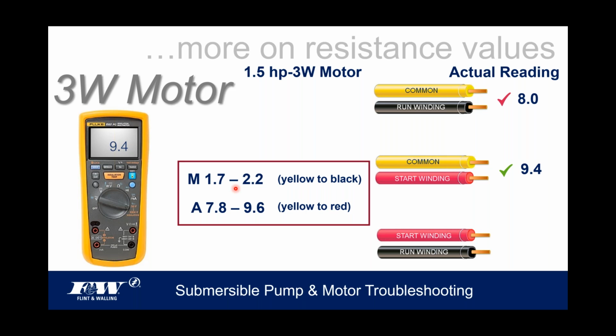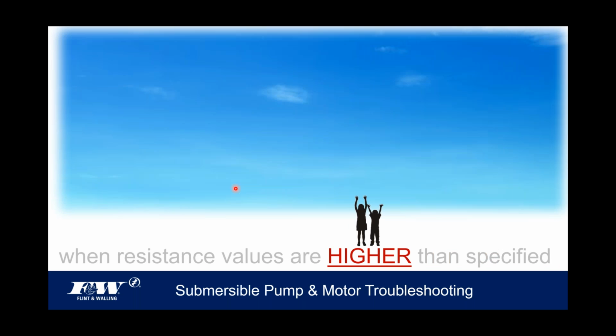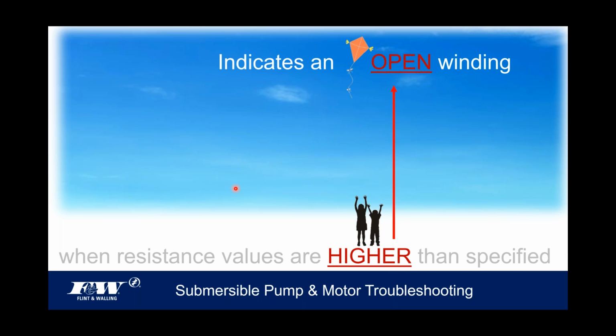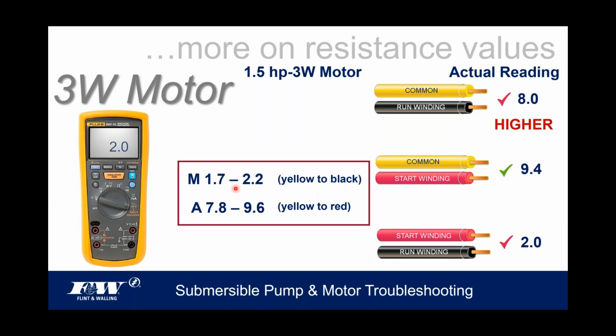What I'm about to tell you would not matter whether I failed on the top one or in the middle one. The key is this: anytime the resistance values are coming in higher than specified, how do we equate to what that is? Well, I thought about this for a while. I'm going to admit it's rather corny, but I remember it this way. If I want to think of something that's higher, I walk outside and look up. That's pretty daggone high. What am I looking at? I'm looking at a wide open sky. And so anytime we get resistance values that are higher than the specified values, think of that open sky, because if they're higher, that's going to indicate an open winding.